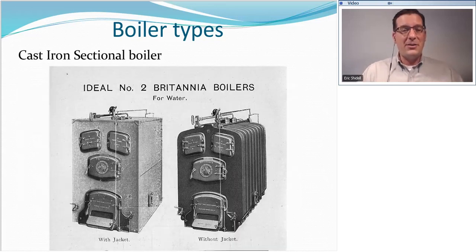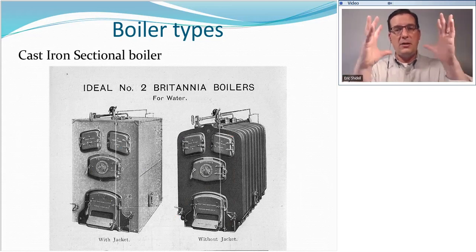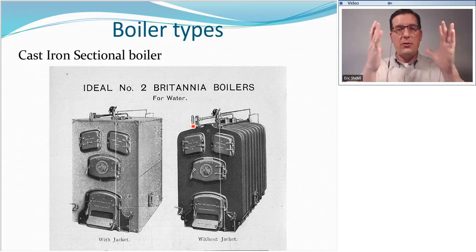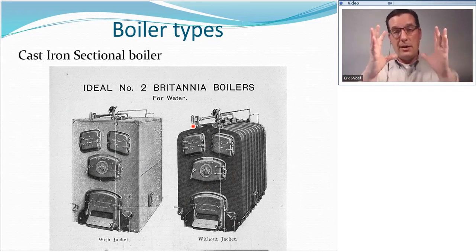Let's look at some of the old ones. Here's what we call the Britannia boiler. These are really old. These are coal-fired, by the way. And you still see boiler sections. You see them all, 1, 2, 3, 4, 5, 6, 7, about 10 of them. You can see they're bolted together. There's a draw rod right there bolting all these sections together. There's another draw rod there, and there's a third one down here in the corner, and a fourth one up here on the top. And this is basically squeezing all those sections together so that the waterways remain watertight.